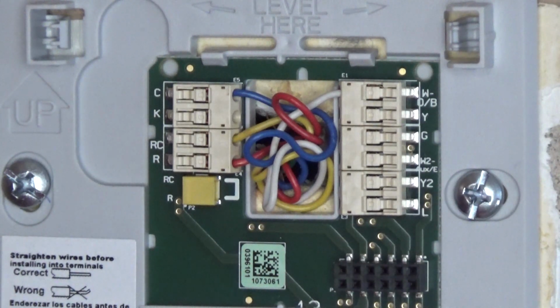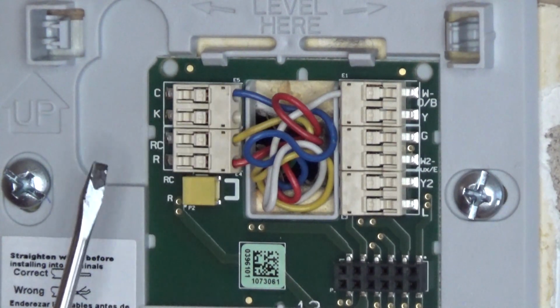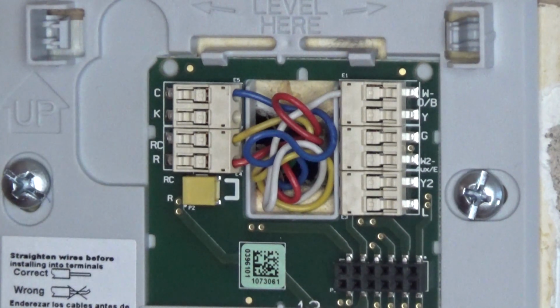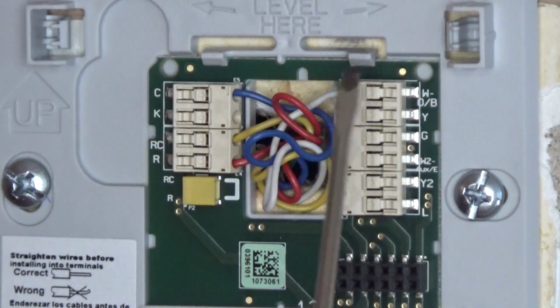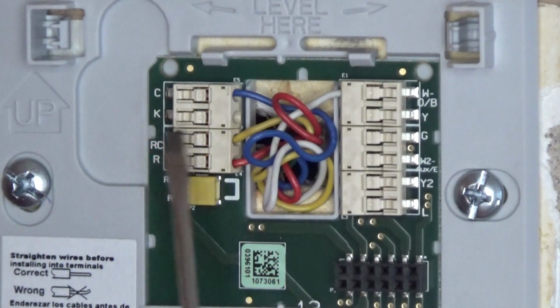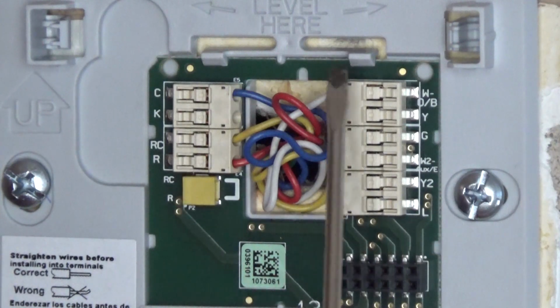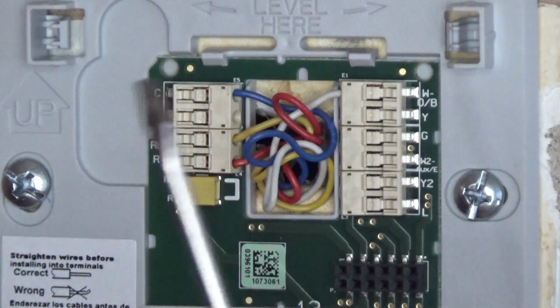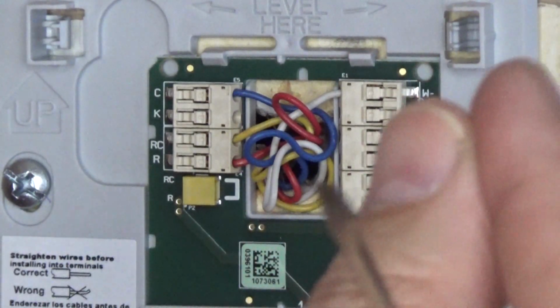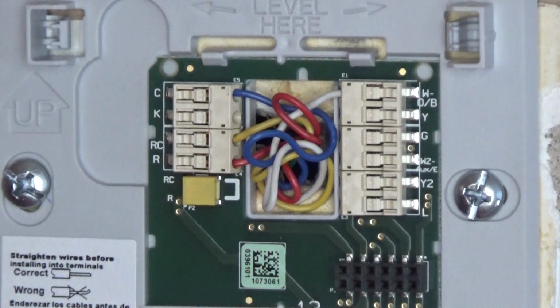Okay guys, we're back upstairs. As you saw, we have two 24 volt feeds, one that shuts off with the boiler, and one that is constantly on as long as there's power in the house. So from the 24 volt transformer, we have the blue wire and the yellow wire, which became our common wire and our RC wire. That feeds the system itself. The system needs 24 volts regardless. That's why it's not battery operated. The furnace wires are the R wire and the W wire. The R wire is a 24 volt feed and the white wire is the return. So when the system kicks on, it closes that contact and feeds the system back down.